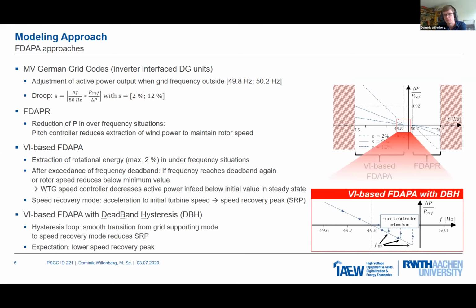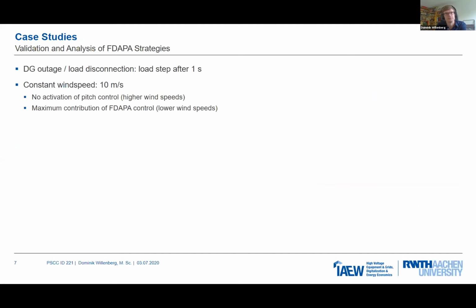Especially in grid parallel operation, to overcome this issue with the speed recovery peak, VI-based concepts with, for example, deadband hysteresis are used. So the idea here is that a smoother transition from this grid supporting mode to speed recovery mode is possible, and this is done by just shifting this limit frequency closer to the nominal frequency, in this example 50 Hz, and to expect a lower speed recovery peak. So now, to analyze the different impacts of the different control approaches, case studies are performed.